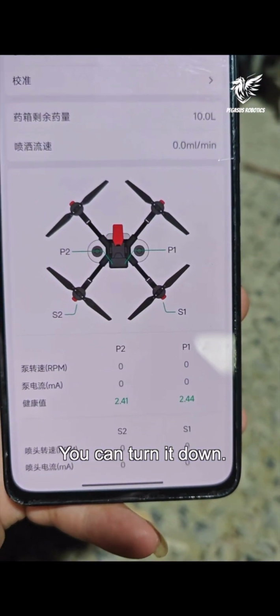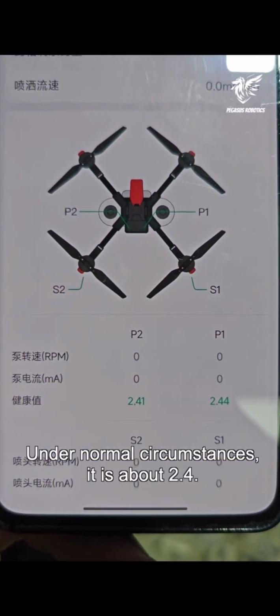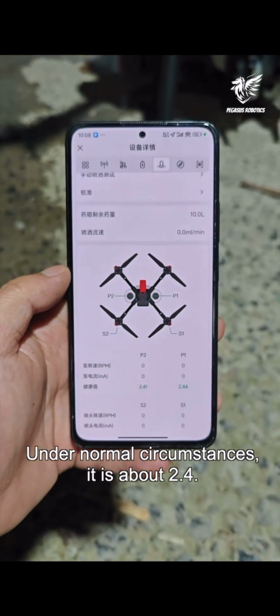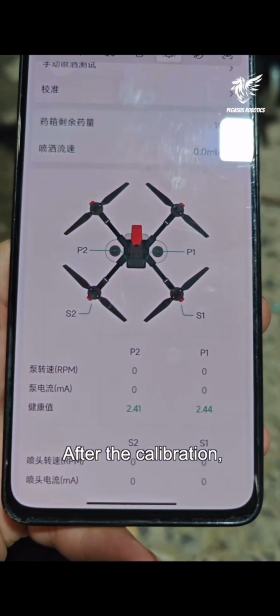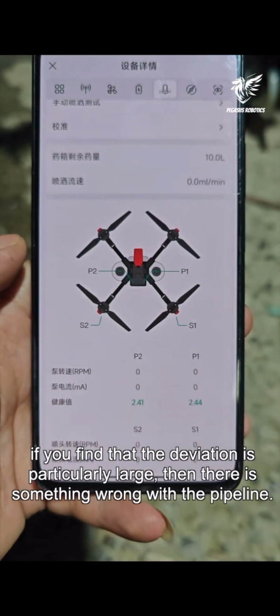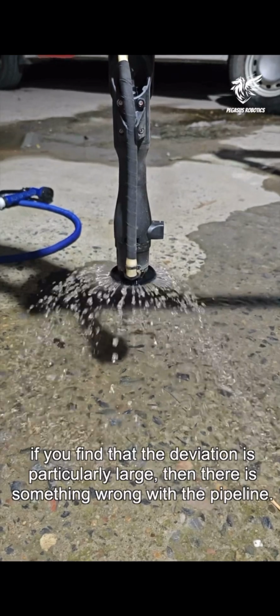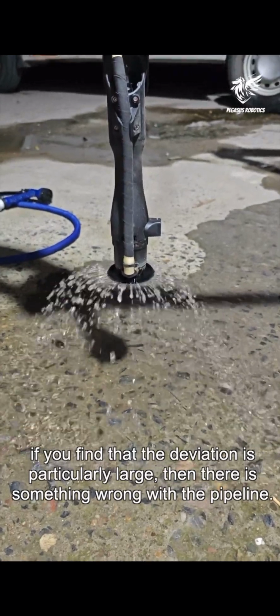You can turn it down. Look at the health value. Under normal circumstances, it is about 2.4. After the calibration, if you find that the deviation is particularly large, then there is something wrong with the pipeline.